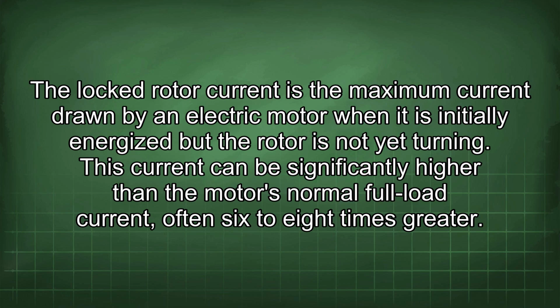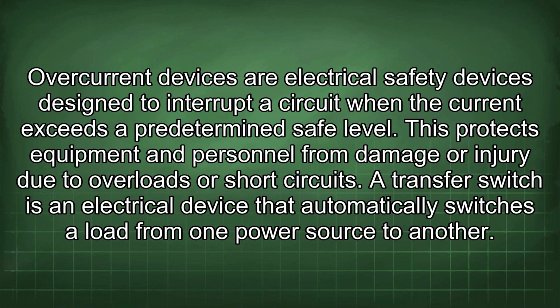The locked rotor current is the maximum current drawn by an electric motor when it is initially energized but the rotor is not yet turning. Its current can be significantly higher than the motor's normal full load current, often 6 to 8 times greater. Overcurrent devices are electrical safety devices designed to interrupt a circuit when the current exceeds a predetermined safe level. This protects equipment and personnel from damage or injury due to overloads or short circuits.